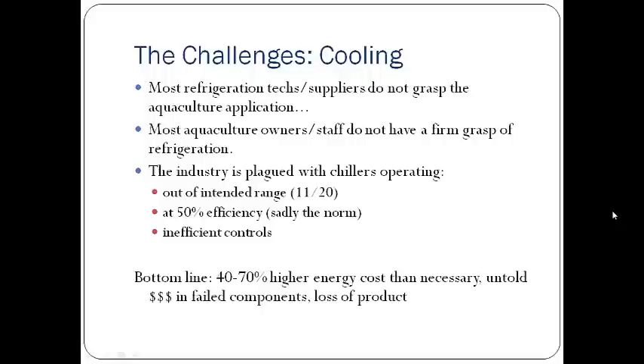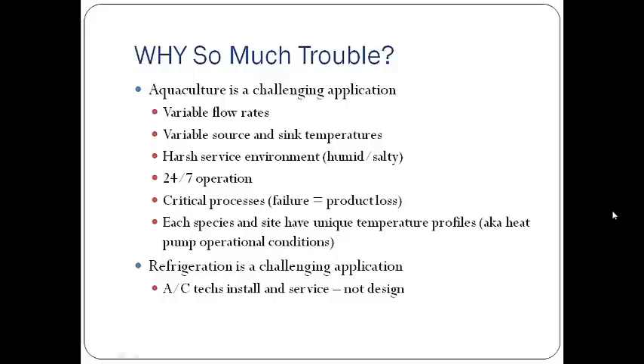Being operated outside of the intended design range often results in higher maintenance costs, failed components, and in the worst cases, loss of product. Why is there so much trouble in this specific application? Well, aquaculture, especially hatcheries, have variable flow rates, variable temperatures. Bring in ambient water that could have a wide range from winter to summer. Ambient air, if we're using that as a source or sink, could change drastically. Target temperature often stays the same, but between different sites, different species, that would change as well.